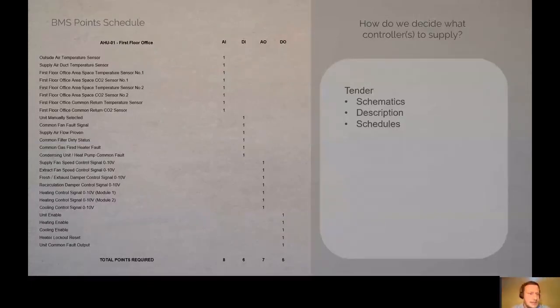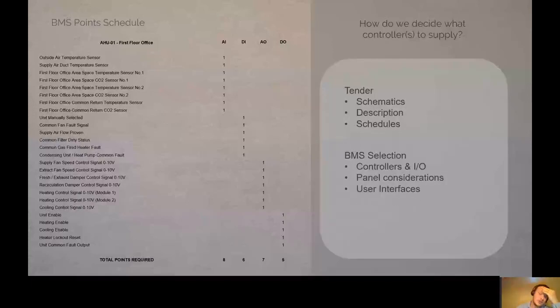Thank you. So in this instance, it's an air handling unit. We've identified a number of analog inputs denoted AI, a number of digital inputs denoted DI, and so on with analog outputs and digital outputs. That allows us to create a comprehensive selection so we can identify what controllers we need and the input and output modules that will provide the control for that - any panel considerations based on the voltages we're dealing with, any user interfaces, as well as network requirements.